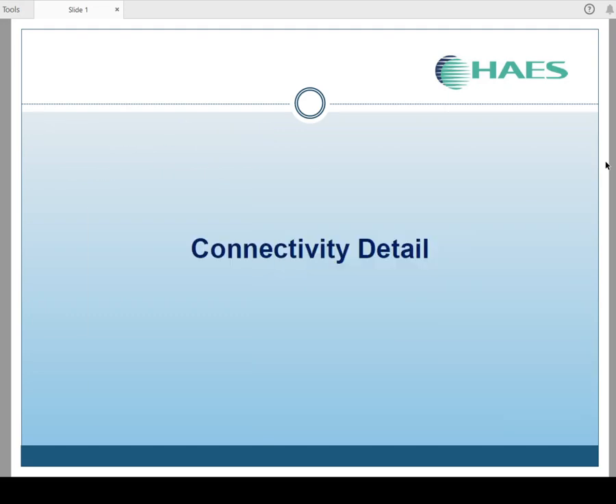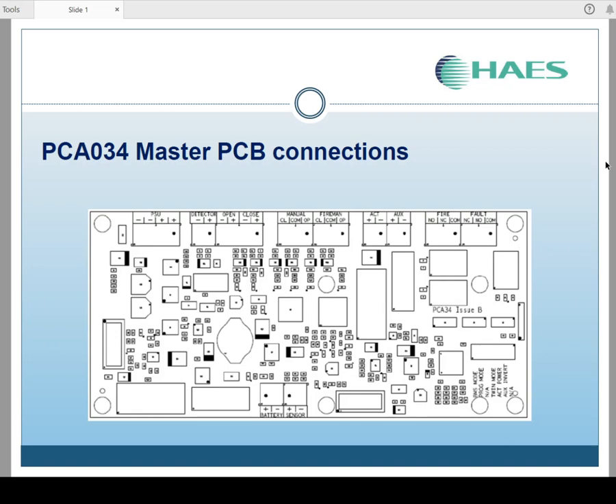Connectivity details. Here we are looking at a picture of the main PCB inside the panel. Starting along the top edge there, up the left hand end, we've got our power supply input that will be pre-wired to the power supply unit inside. Moving to the right, we have our detector pos and neg. This circuit can be set as twin wire if you require it, so you can put sounders on the same line as your detection.